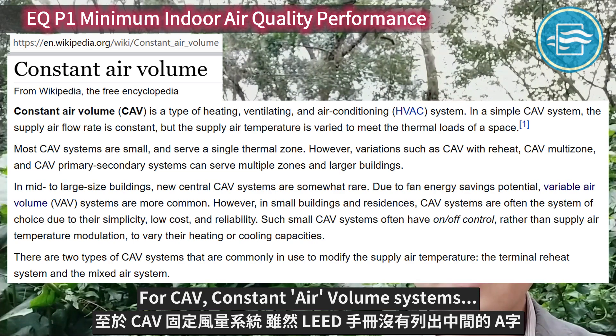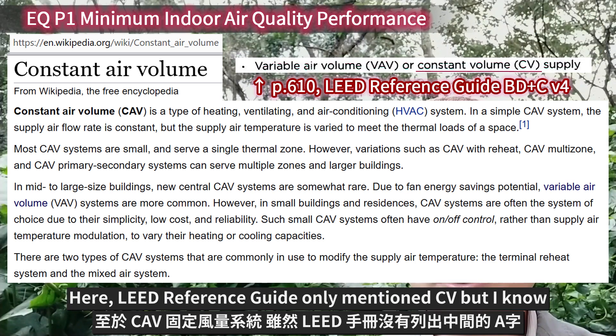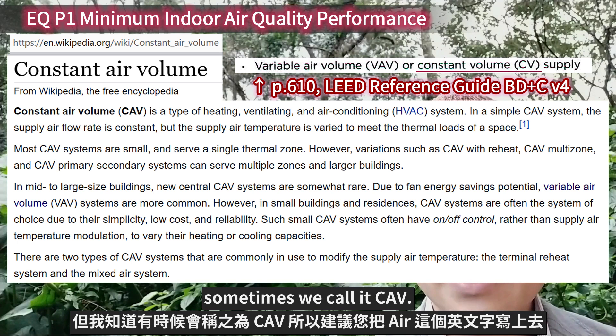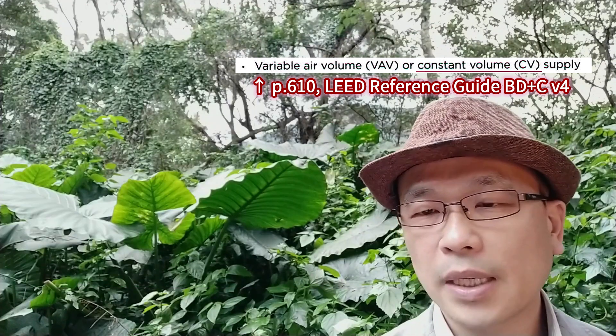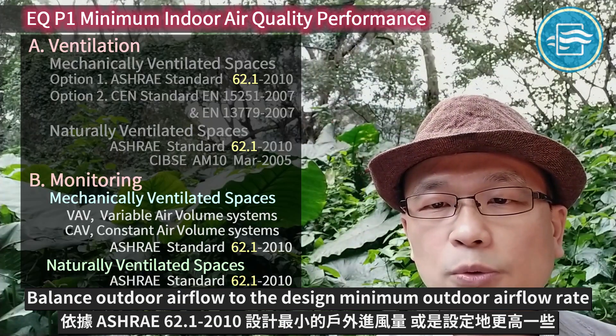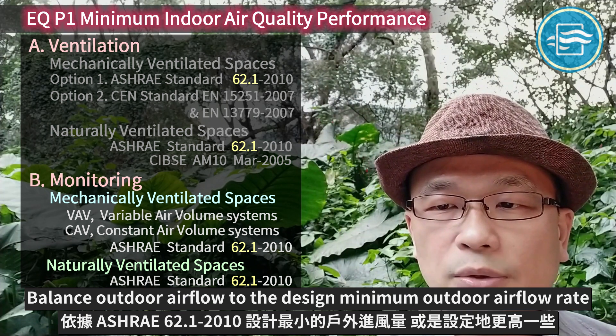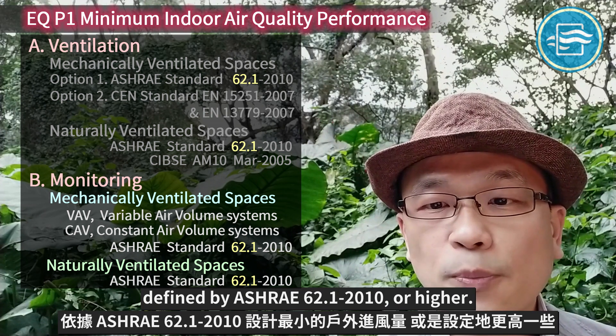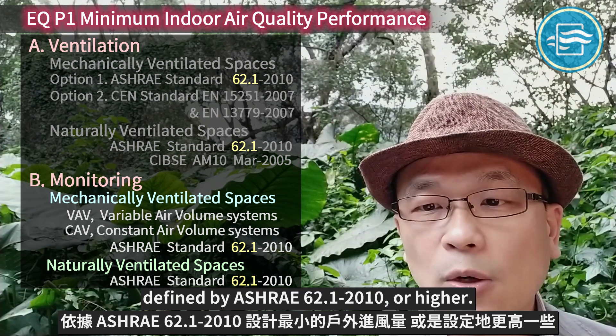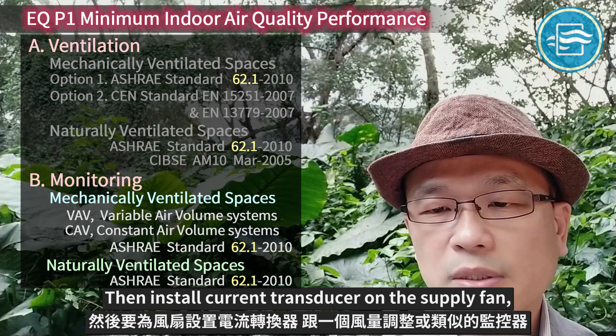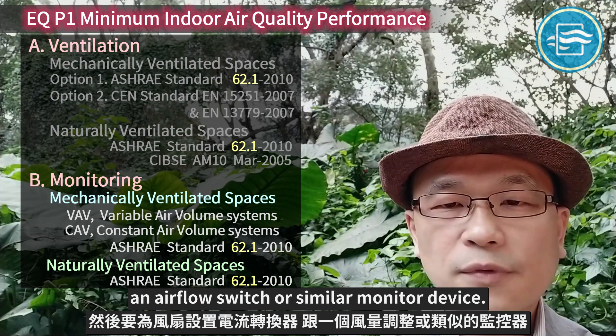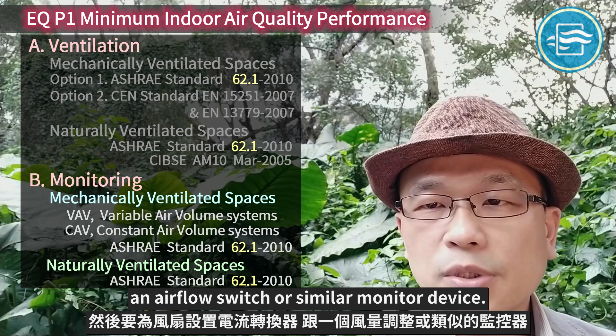For CAV — Constant Air Volume systems — balance outdoor air flow to the design minimum outdoor air rate defined by ASHRAE 62.1-2010 or higher. Then install a current transducer on the supply fan, and an air flow switch or similar monitoring device.